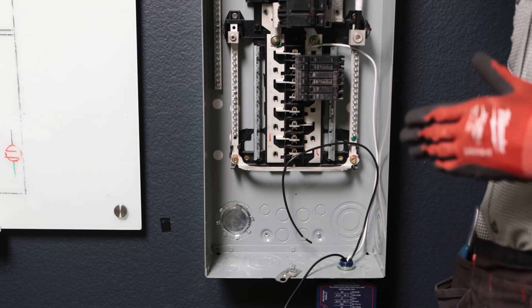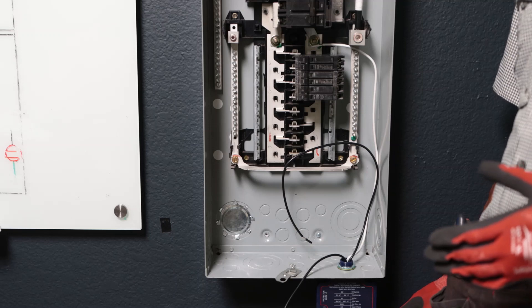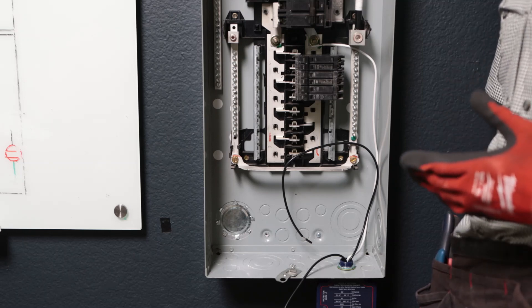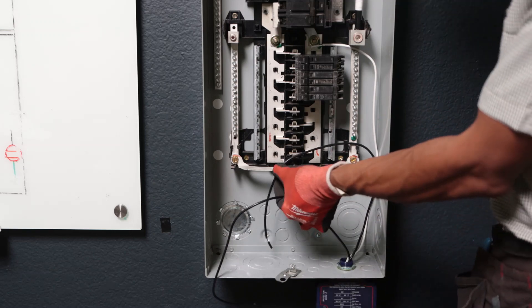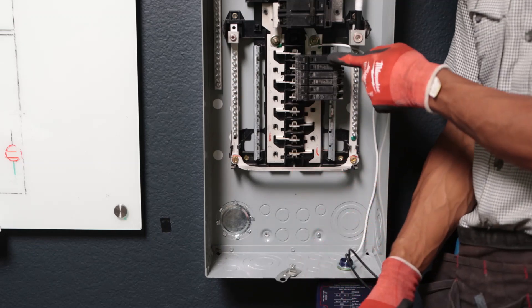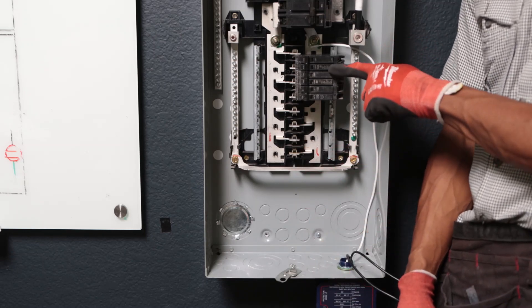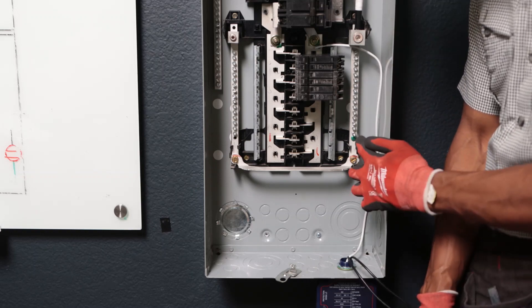Last but not least, what I love about the ICM 518 model is that it can be wired up as type 1 or type 2. For this particular installation, we're going to be wiring it up as type 2, which means we'll use a double-pole breaker. To make it short and simple, these two black wires will go onto this double-pole breaker — one wire under one screw, the other wire under the other screw. This white wire will go on the neutral bar.